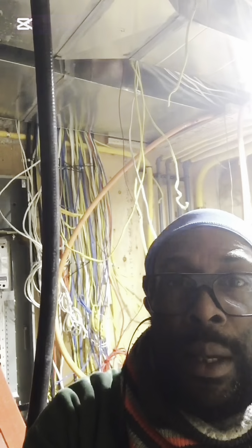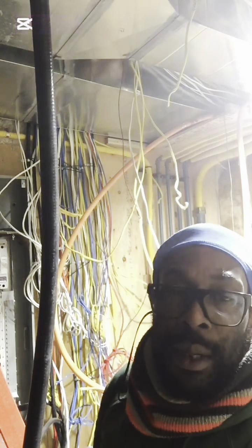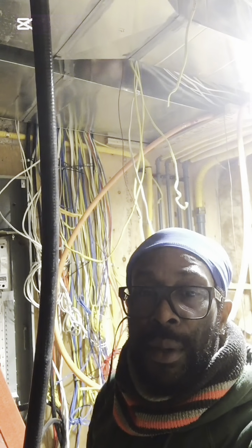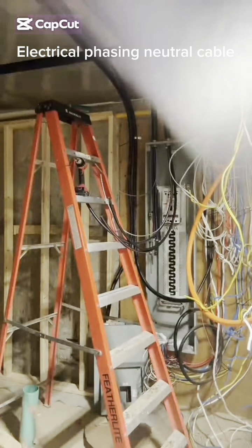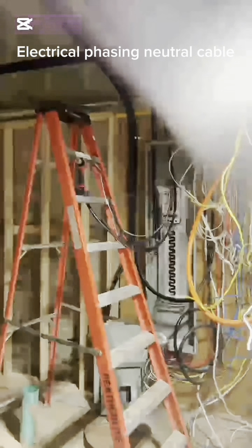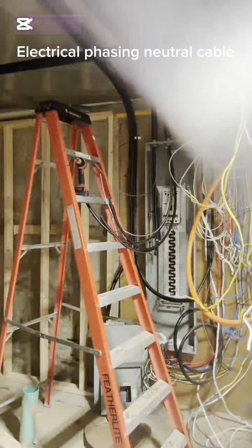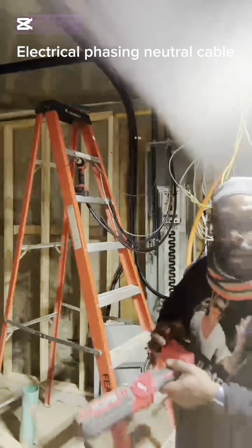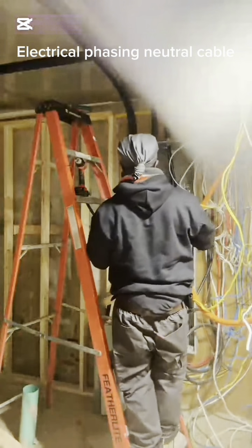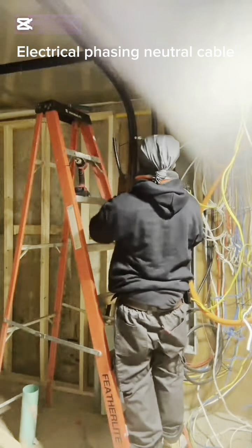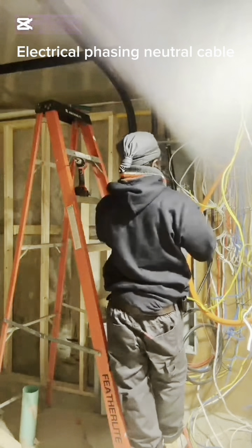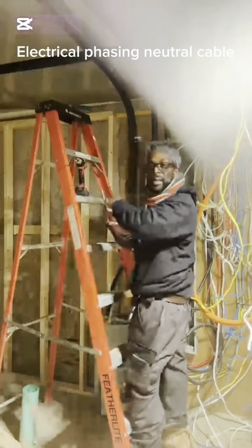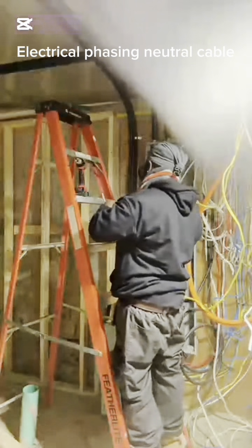The cardboard you saw on top of the 400 amp breaker is to protect the breaker from receiving shavings once I start drilling. Those shavings shouldn't enter the panel, any part of it, as it will affect the panel's actual working. So when I'm drilling into the 400 amp panel, or even a 100 amp panel, or a transformer of some sort, I like to cover the main components to make sure nothing enters it.